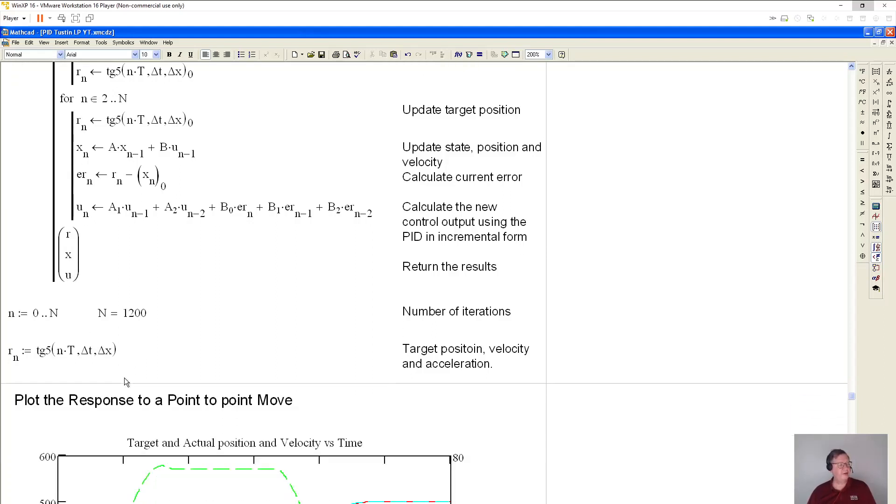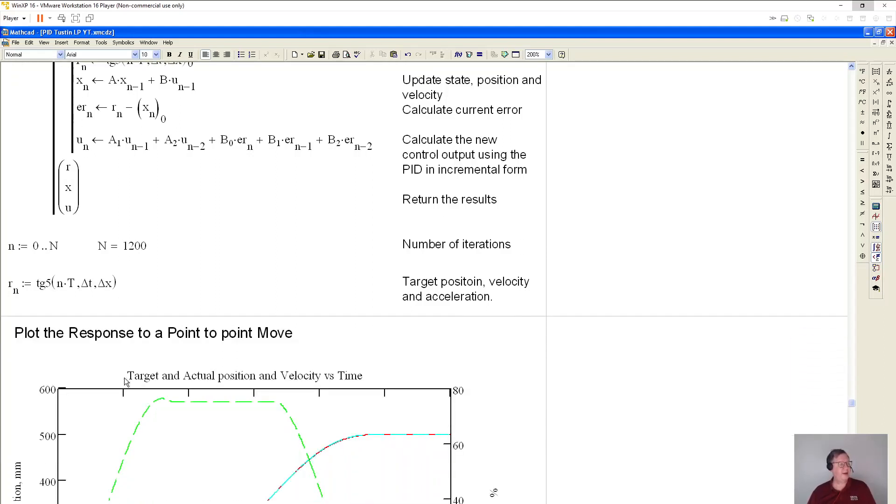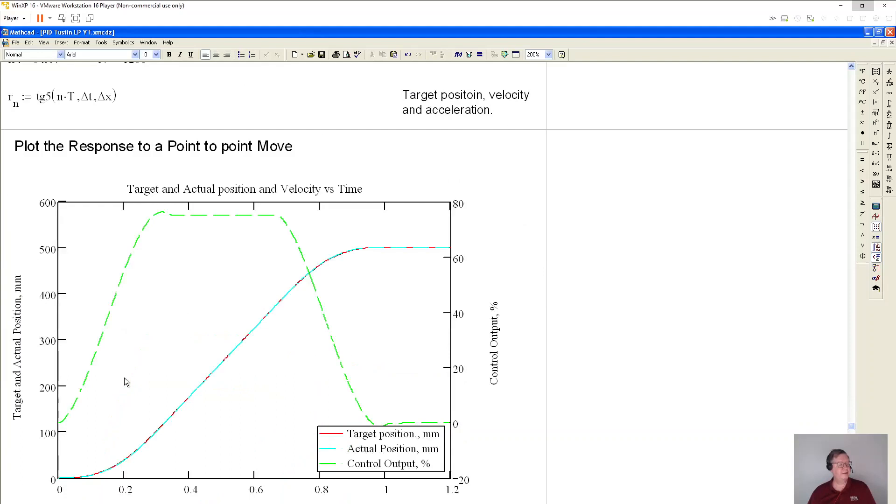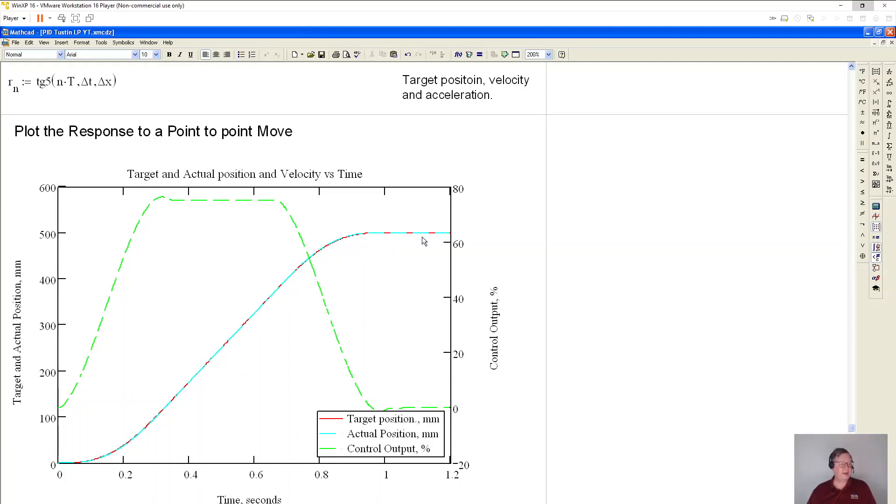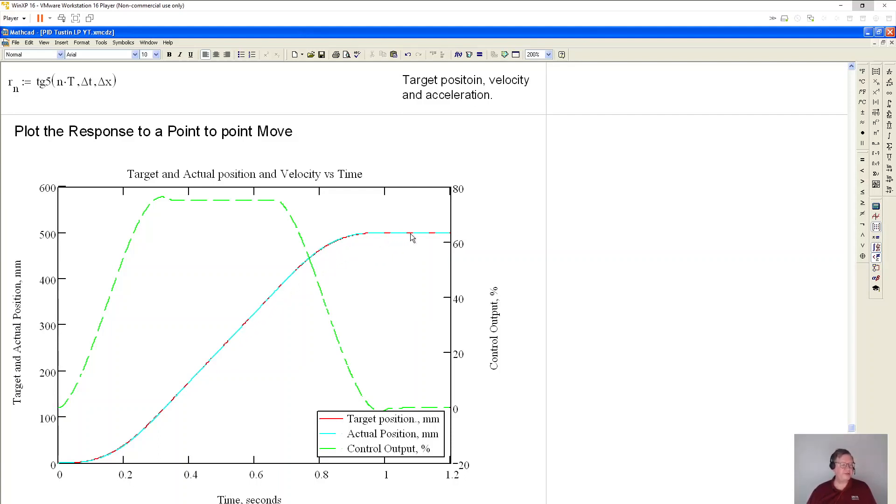So let's see how I did. And you can see that this is a plot of the target and actual position. And it's color coded here, the target position is the red underneath. And the actual position is the blue on top. And we can see that they overlap each other, which means that they're following very close. And I did all this without using feed forwards. So you know that the tuning and the PID is working well.